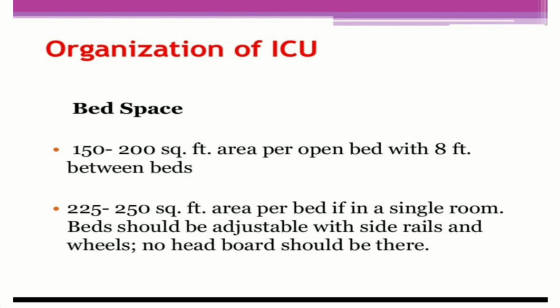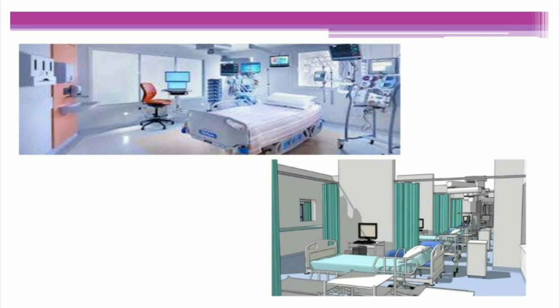Bed space is 150 to 200 square feet per open bed with 8 feet between beds. So 225 to 250 square feet per bed if a single room. The bed should be adjustable with side rails and wheels. No head board should be there. So this is the area where we have to give patient care.